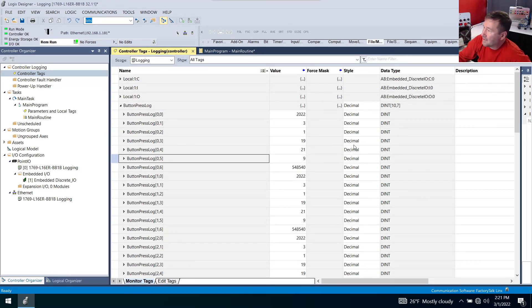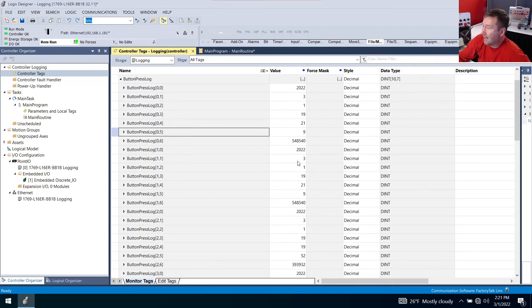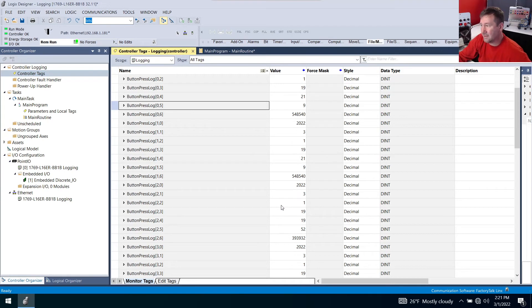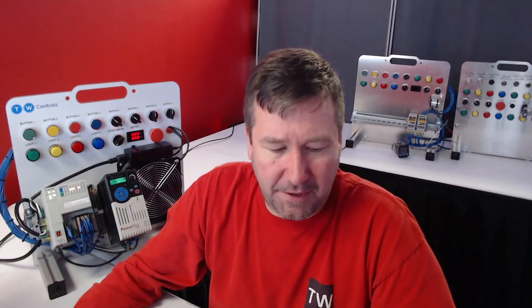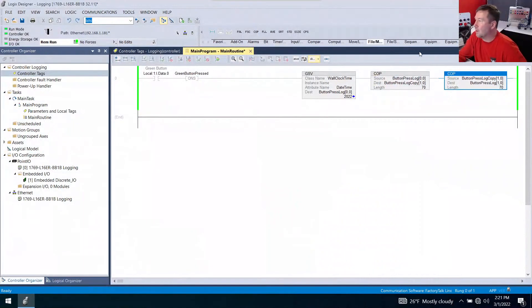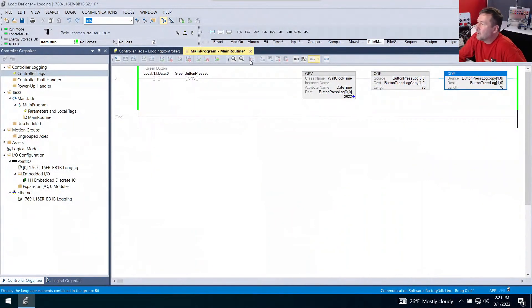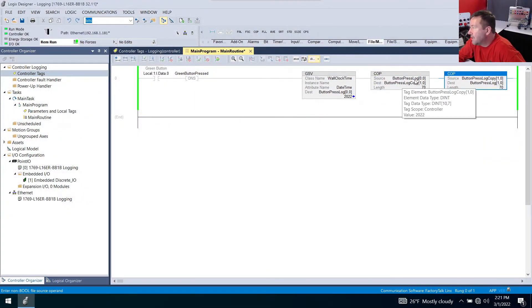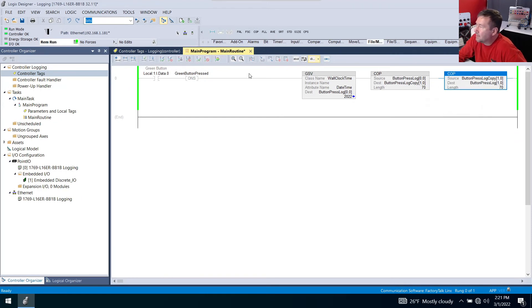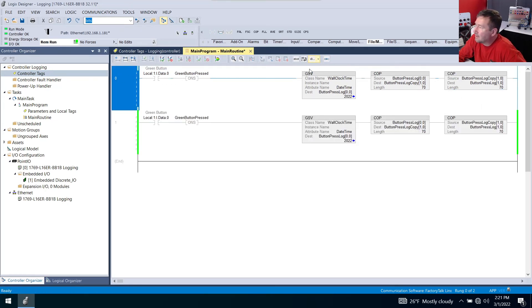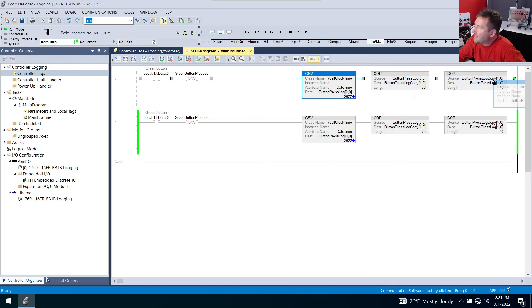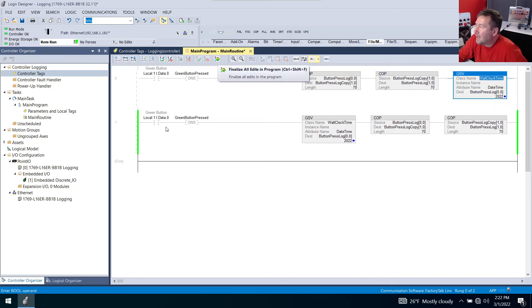As now the time is 19, 21, 9. And the second time is 19, 21, 9. But then we seem to go in the right order after that. And this has to do with the order of operation, really. So let's focus on this program here. As first, right now we're reading the time and then we're moving it and doing our shift here. What we need to do is we need to shift and then move our time. So we're going to edit this line and we're going to bring that GSV to the end here. And this is a really good one to study on later to understand how program flow works.